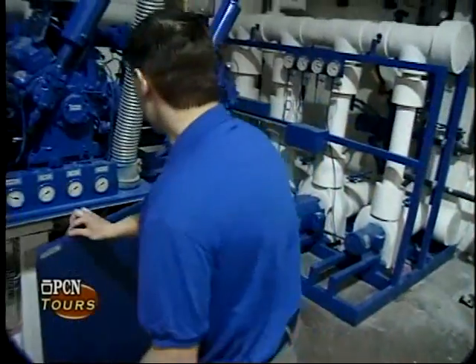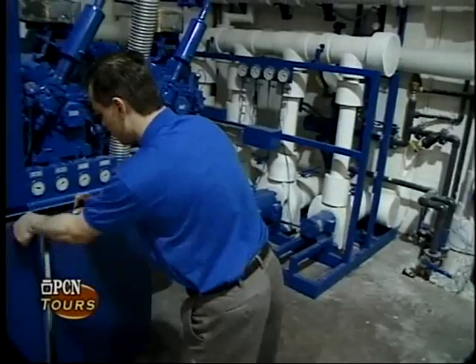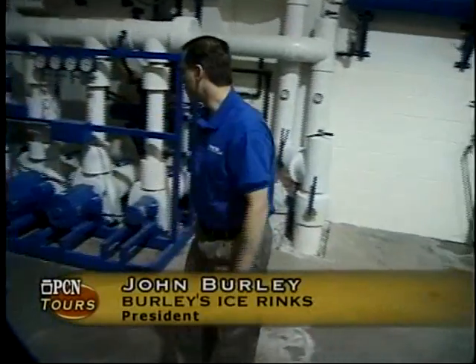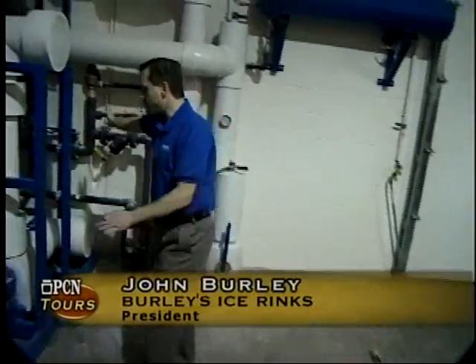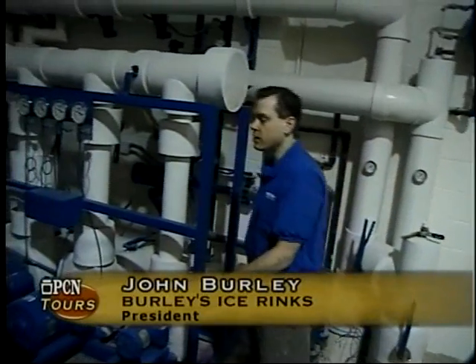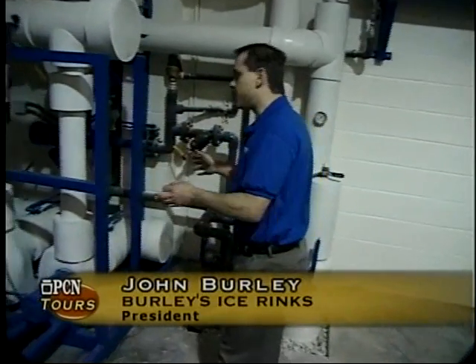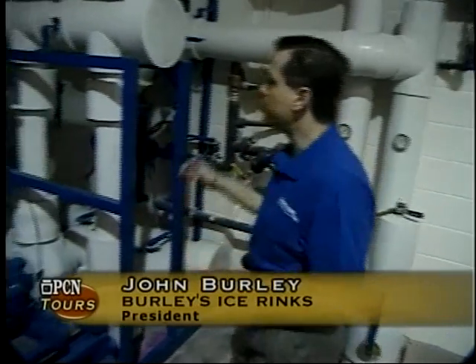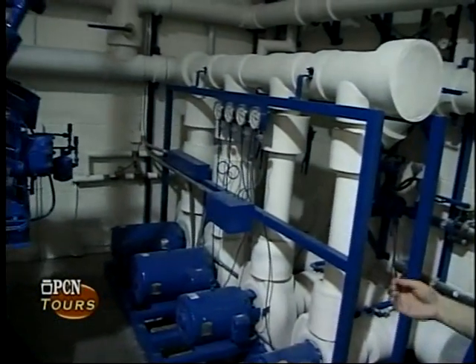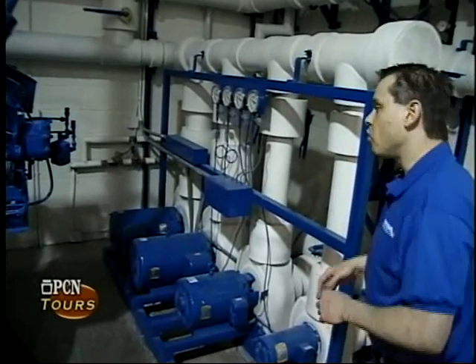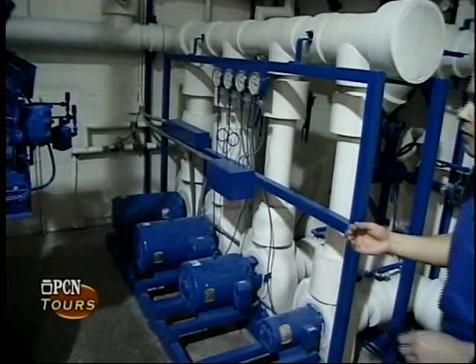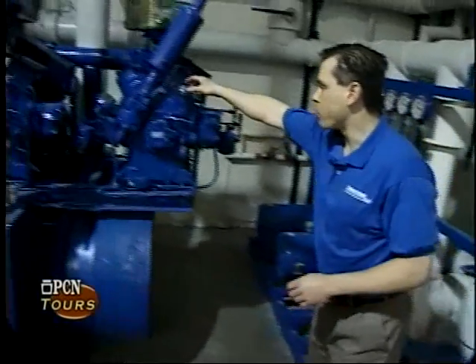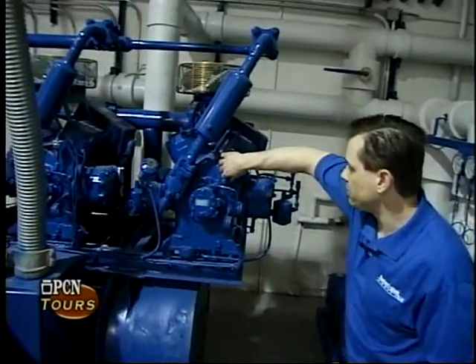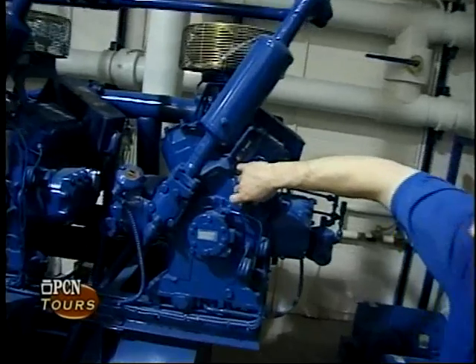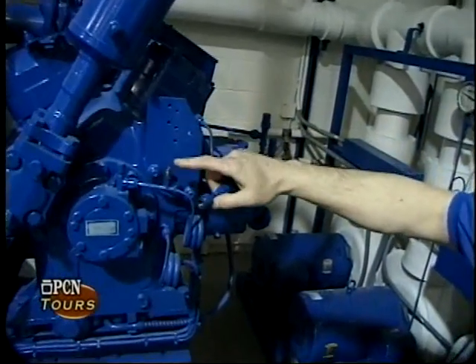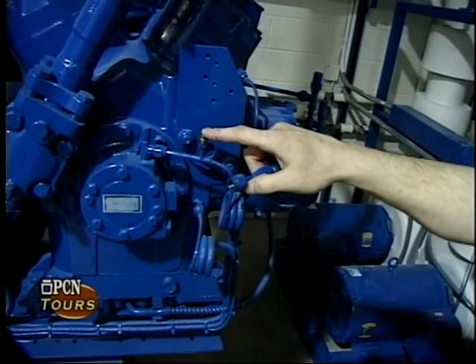The pump skids that you saw downtown being made are here installed, and here you can see how the skid is incorporated into the overall piping practice. The refrigeration system, the pump skid, everything is factory fabricated. When it comes to the site, the amount of interconnecting piping that's required is very minimal. We try to look at service being a big factor, to make sure it's easily serviced. Little things, for example, like the pressure transducers for the microprocessor control system: if something goes bad or is a problem, they can simply unscrew it like this and put a new one in. We have a valve right into the refrigerant system, so they don't have to worry about having any type of refrigerant leak.